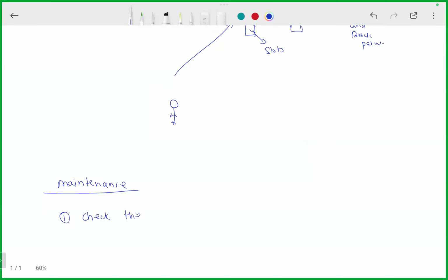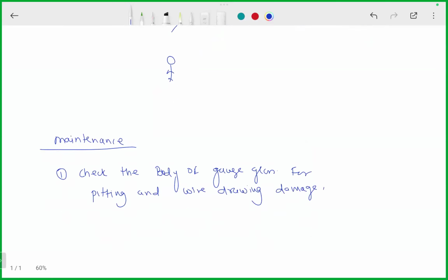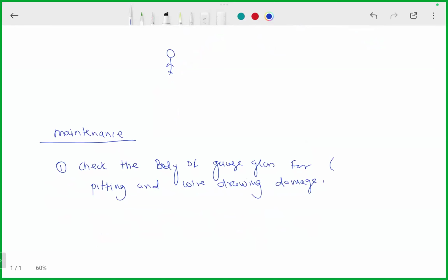Check the body of the gauge glass for pitting and wire drawing damage. The body is made up of either steel or monel metal.